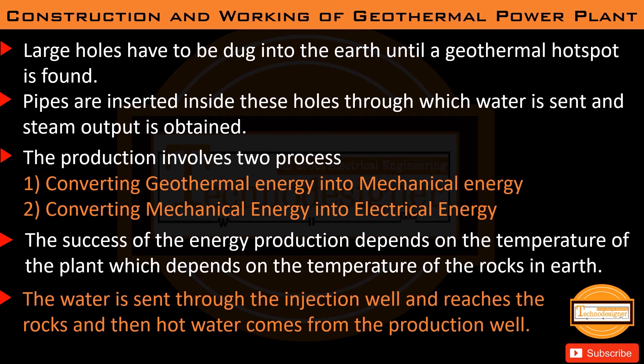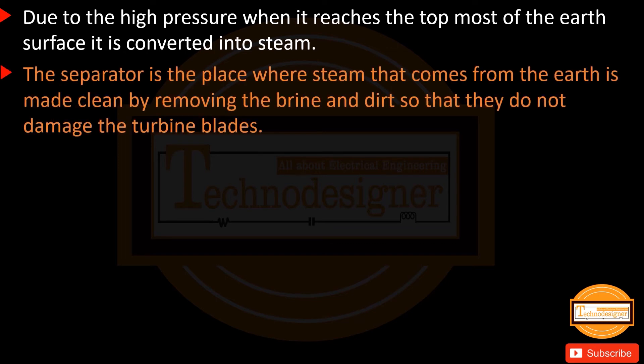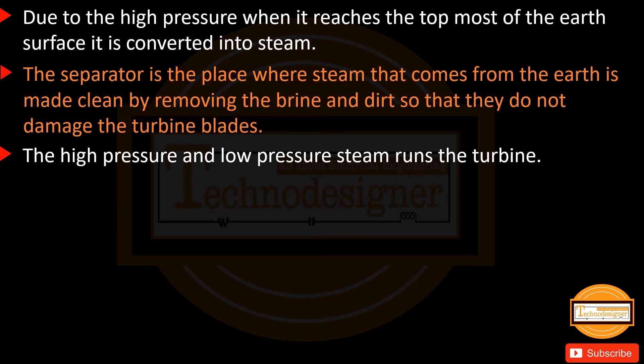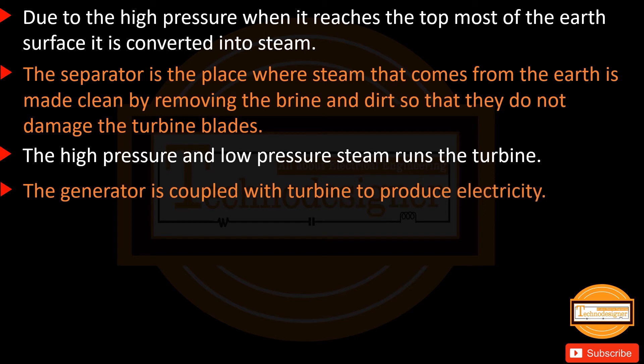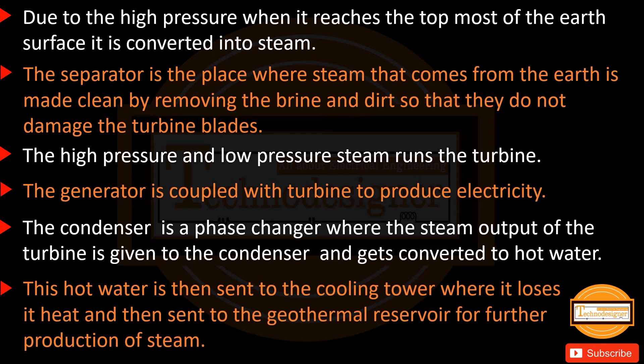Water is sent through the injection well, reaches the hot rocks, and hot water returns via the production well. Due to high pressure, when it reaches the Earth's surface it is converted into steam. The separator cleans the steam by removing brine and dirt to protect turbine blades. High and low pressure steam runs the turbine, and the generator coupled with the turbine produces electricity. The condenser converts steam output to hot water, which goes to the cooling tower and then back to the geothermal reservoir.